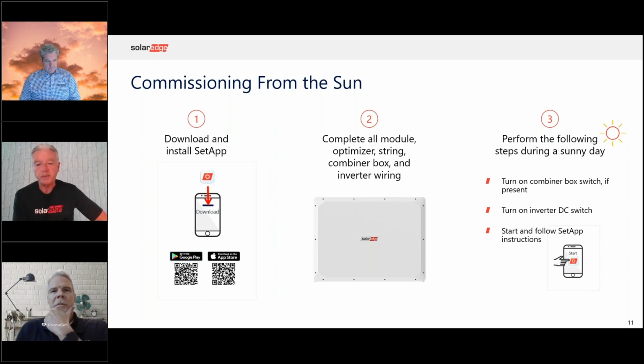Commissioning from the sun is a feature that's built into this inverter. And this is useful when you don't have AC power present at the site. So what you do is you download and install the SetApp application on your phone, and you complete all of the wiring for the inverter, especially on the DC side. You complete all the module, all the optimizer wiring, all the string wiring, the combiner box wiring, all of that. And then you turn on the DC circuit, and then you just follow the normal steps that you would. And you have to perform all of those steps during a sunny day, of course.